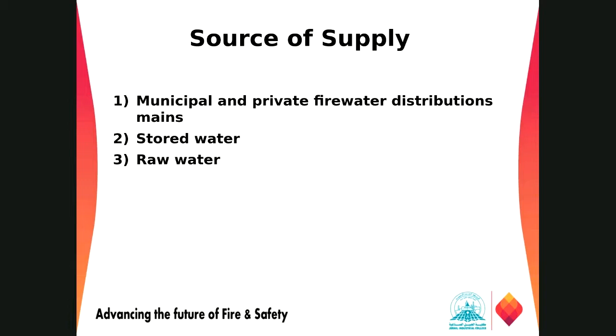For the municipal water supply, we have to make sure that the test data, the hydrant flow test data, is not older than 1 year. So the validation for that is 1 year, right? And when we are considering the public water supply for our fire protection system, some possible variances should be reviewed to determine the relevant impact, like hourly variances in local uses, future growth, municipality supply charges, and true static.